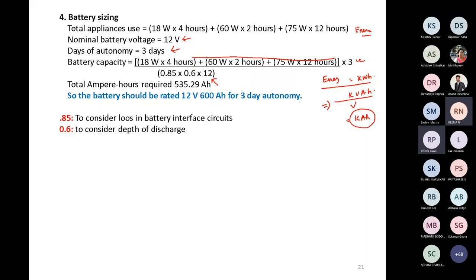Now there are two other factors. One is this 0.85. Whatever energy you are storing in battery, you are not going to utilize it fully to the load, because between battery and your load, you have a power electronic converter. They are not 100% efficient, so you take some extra power in the battery because some power is going to be lost in your power converters. So you take a measure for that.